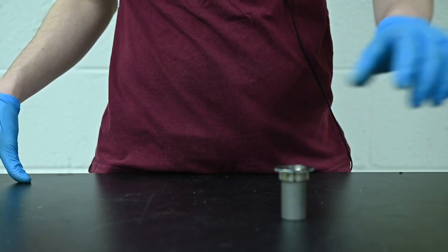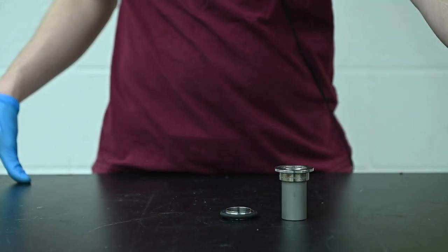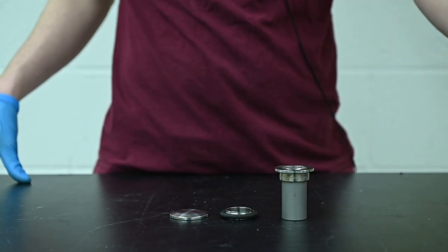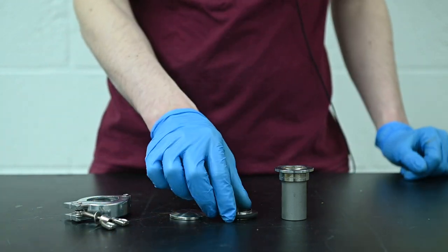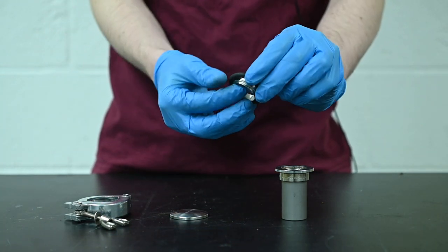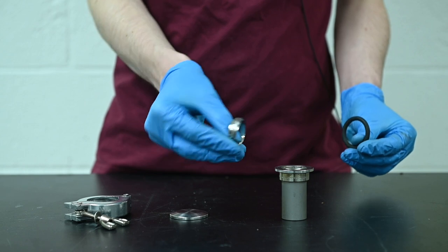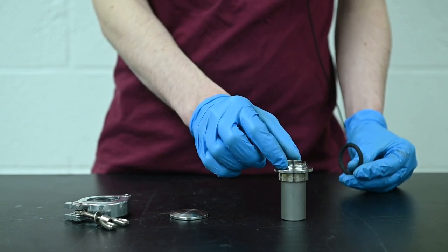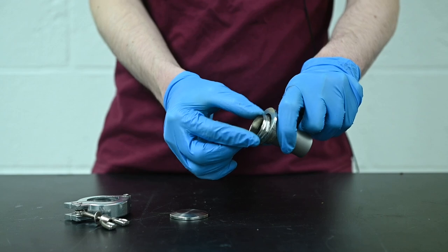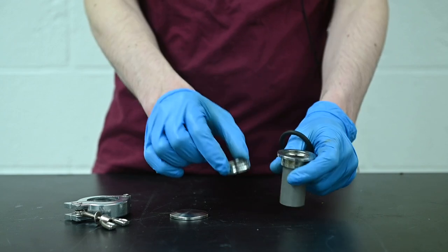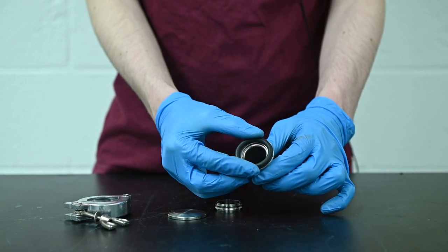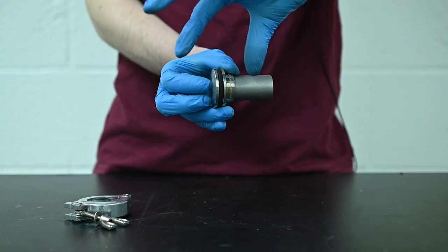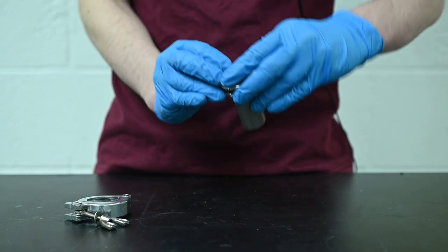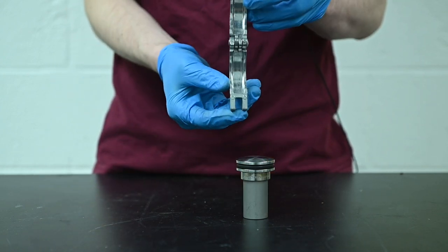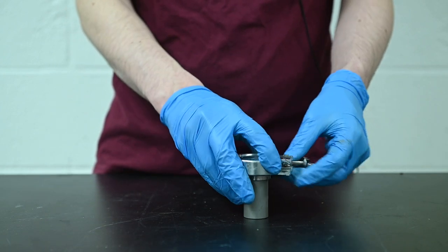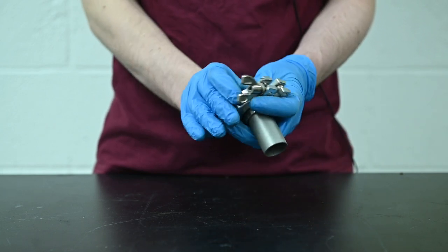Here we see a quick flange, abbreviated KF, also known as an NW flange by other manufacturers. KF flanges are sealed by a Viton O-ring with a centering ring inside, which prevents the O-ring itself from sliding around or being sucked into the center of the vacuum system by the external pressure of the atmosphere. The Viton O-ring snaps onto the centering ring itself, making the whole assembly rigid. It's placed into the counterbore on the KF flanges. The external surface of the KF flange is tapered so that a simple radial clamp axially squishes the O-ring.